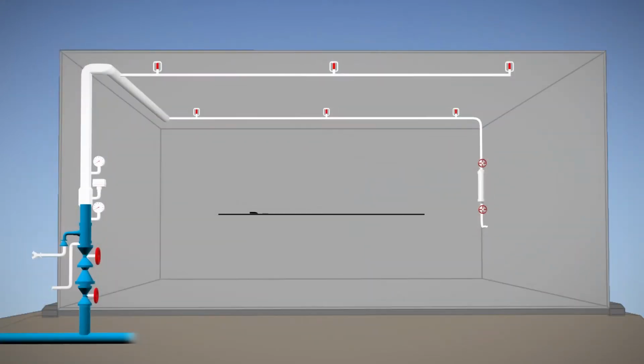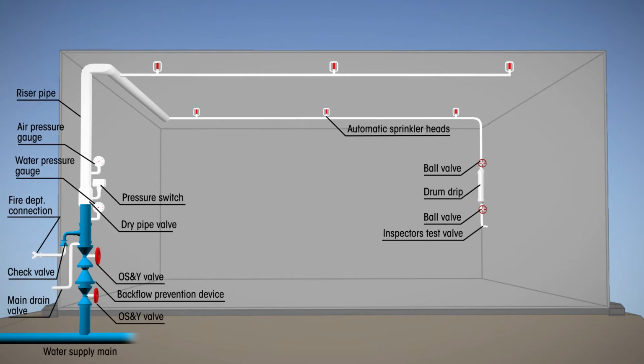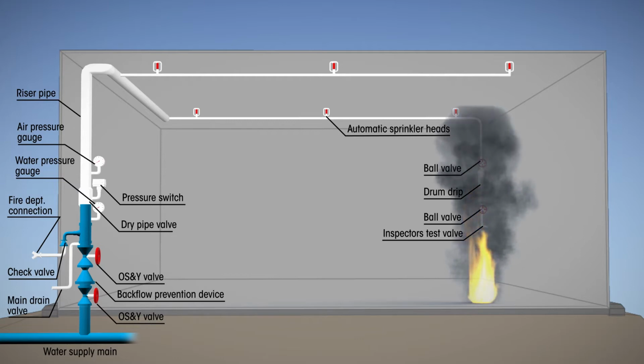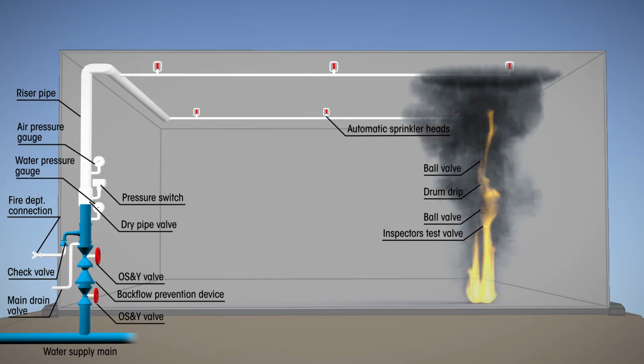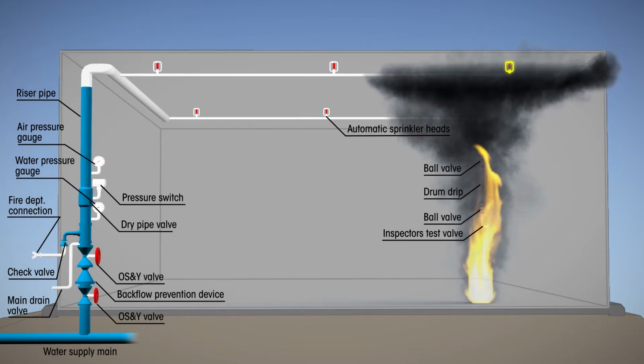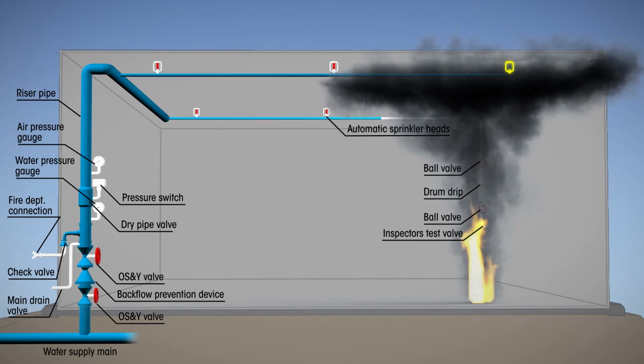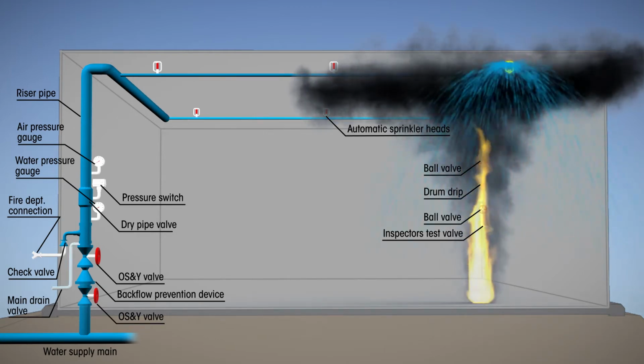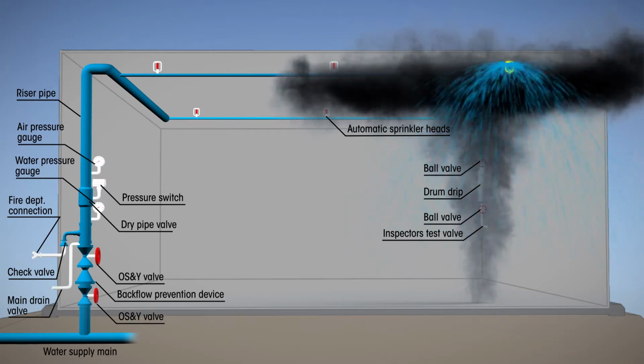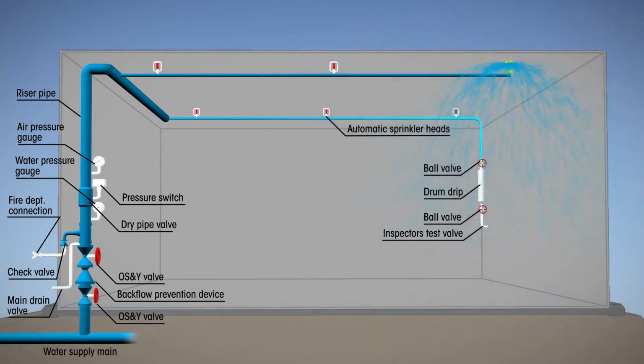Dry pipe fire sprinkler systems have automatic sprinklers that are part of a piping system containing air or nitrogen under pressure. The heat from a fire individually activates the fuse or bulb in a fire sprinkler, causing a release of air pressure. That in turn permits the pressure from the water supply to open the dry valve. Water then flows into the piping and out the activated sprinkler.